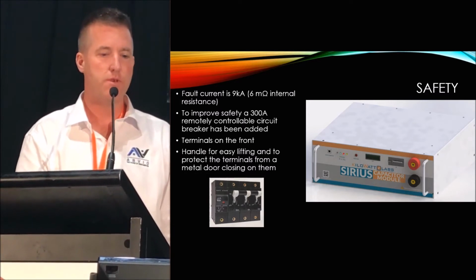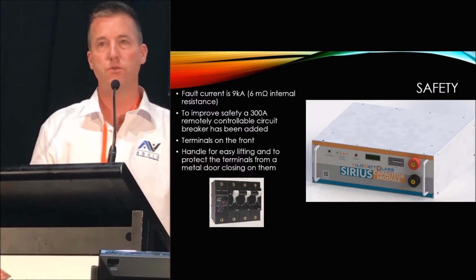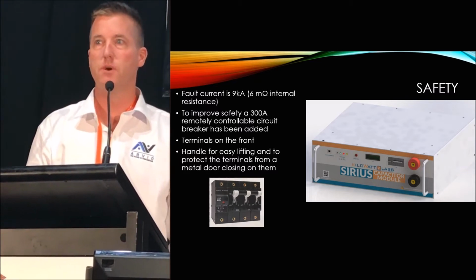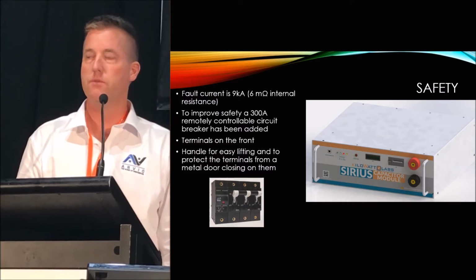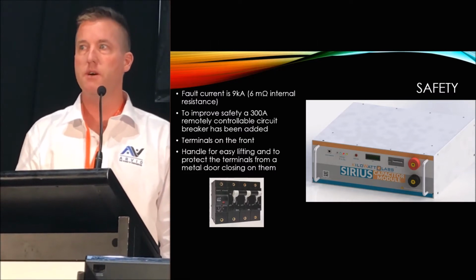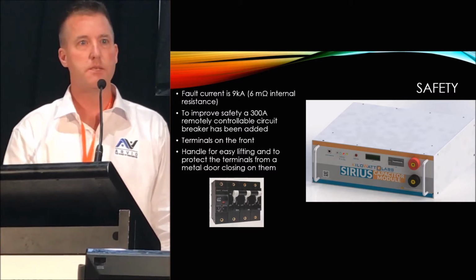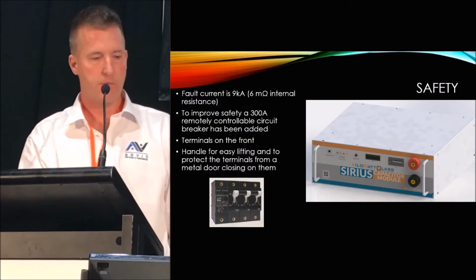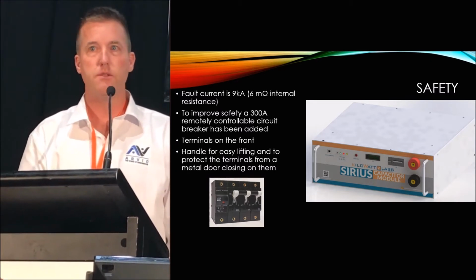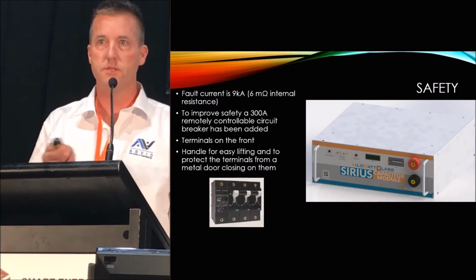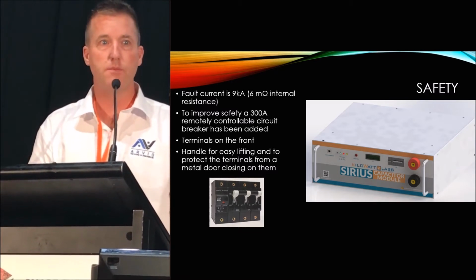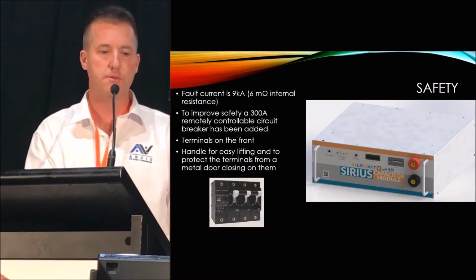So they make circuit breakers, and we worked with them to integrate the 300 amp motorized circuit breaker into the front of the unit, which lets us control the energy storage device remotely. From a commissioning point of view, we can log in to a site away from here and turn off a supercapacitor remotely. So if you have, say, 10 of them in parallel and one sends an email saying it's out of voltage or out of current, we can just turn that one off and the system keeps running.